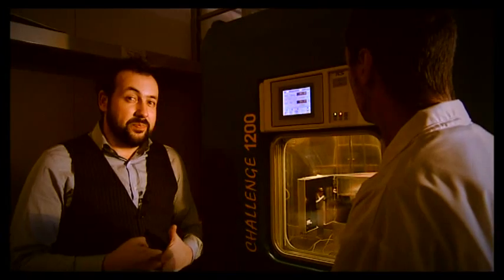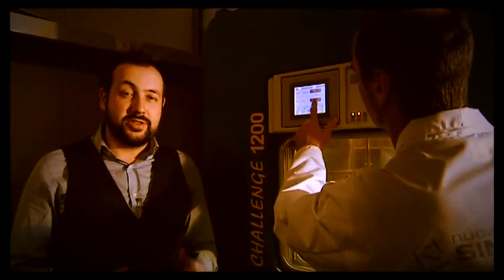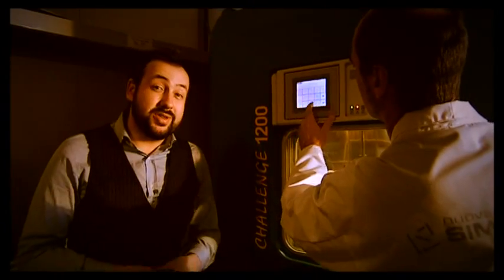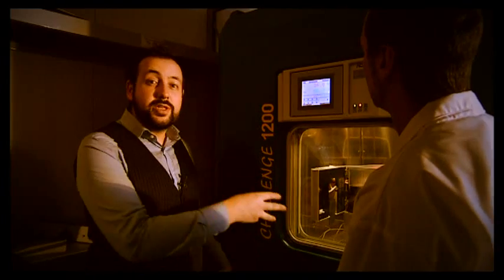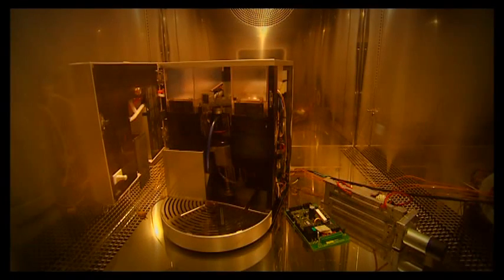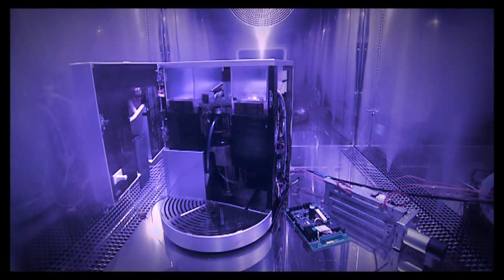This thing is a climatic chamber. What it does is create conditions to test materials. So you can have conditions like minus 15 degrees Celsius to 100 degrees Celsius or 0% humidity to 100% humidity. That's all tracked through a data log with 40 different probes. The idea is that over long periods of time you can find how your materials and machines are going to perform and how reliable they are.